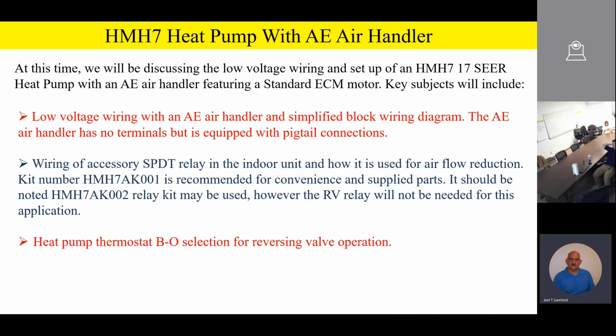At this time, we're going to be discussing low voltage wiring and setup on the heat pump. We're going to start out with an AE air handler, which features a standard ECM motor. Remember, guys, when I talk about the standard ECM motor, I'm talking about the X13 style of motor. You've seen those before, a high efficiency motor with speed taps, 1, 2, 3, 4, 5 speed taps. That's the motor we're going to feature to start out this morning.